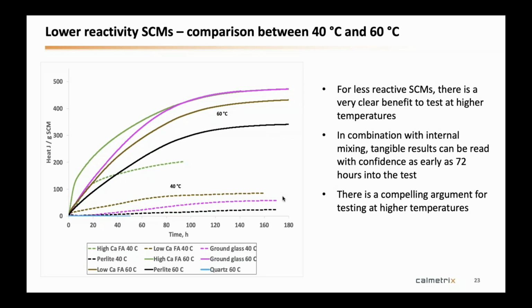Yeah, the only issue, Abdul, I think maybe we've talked about this before, obviously, if you're at the extremes of the temperature range of any of the calorimeters, if your lab is really, really hot and you're trying to go down to really, really cold temperatures, then that becomes more of an issue in terms of temperature control more than anything else. But hopefully we answered that question.